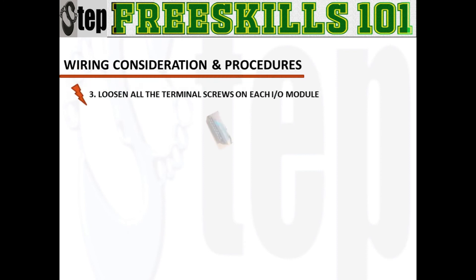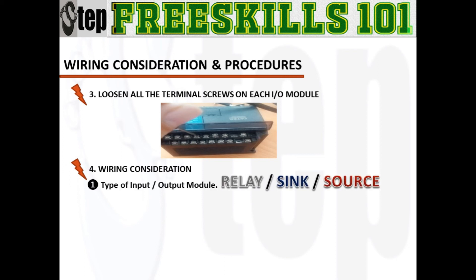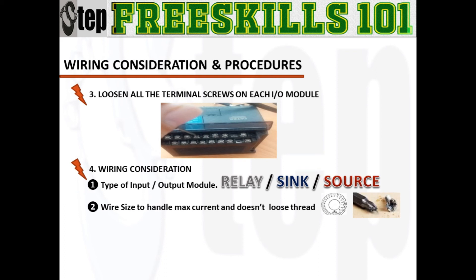Third, loosen all terminal screws for both the input and output modules. Fourth, wiring considerations. Under wiring consideration: first, you need to consider what type of PLC input and output module, to identify its polarity. Second, check also the wire gauge size so you would know its maximum capacity, and also to avoid loose thread at the PLC termination.